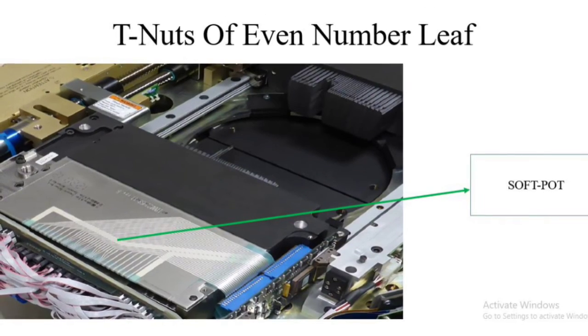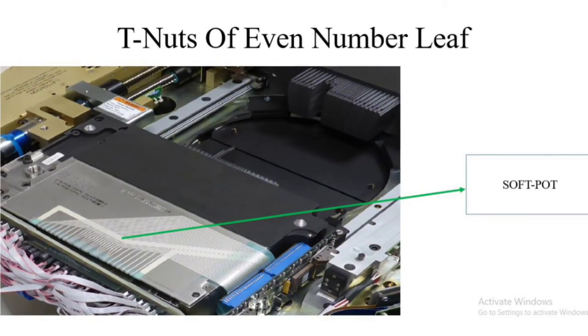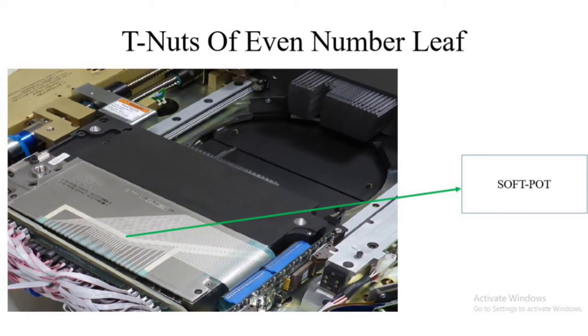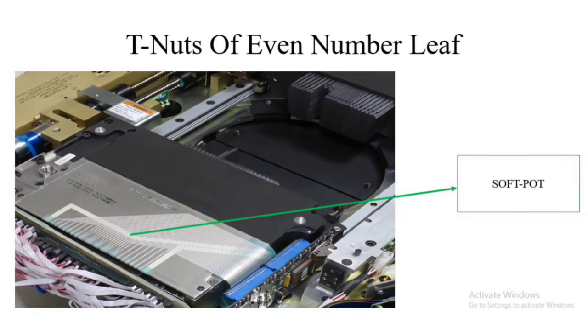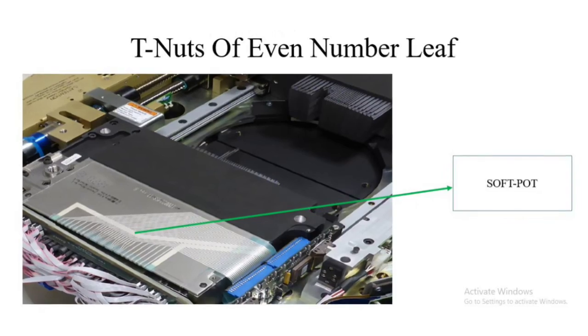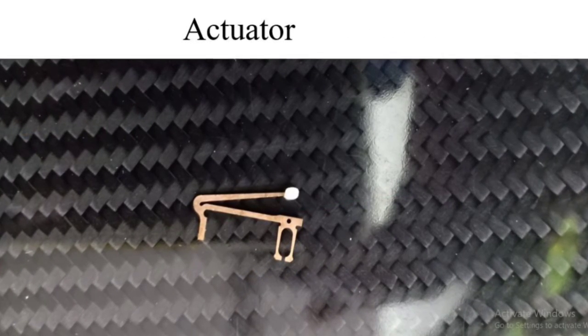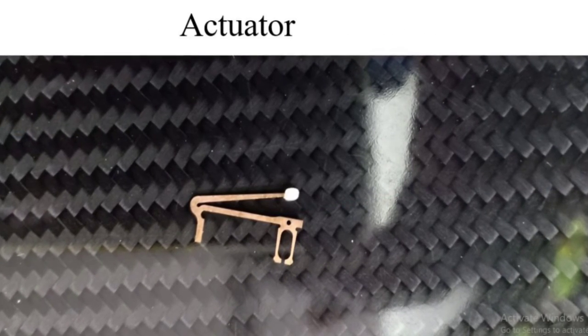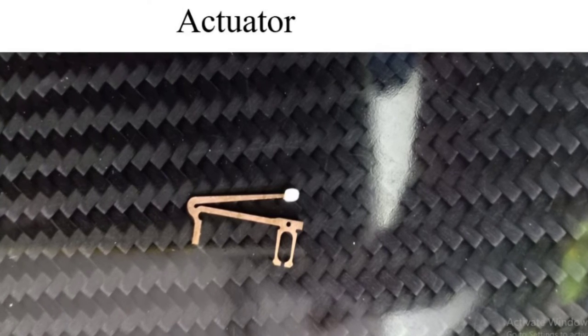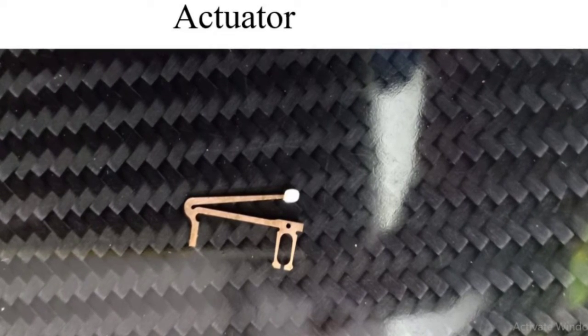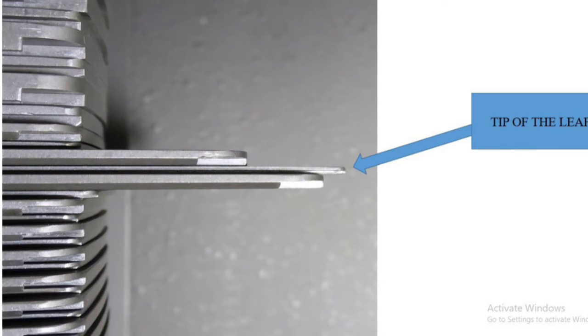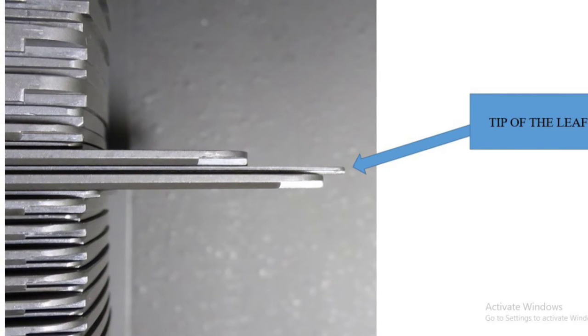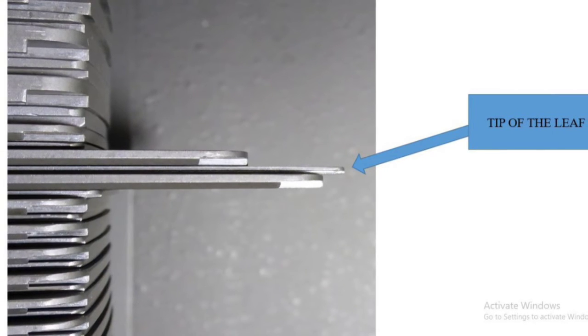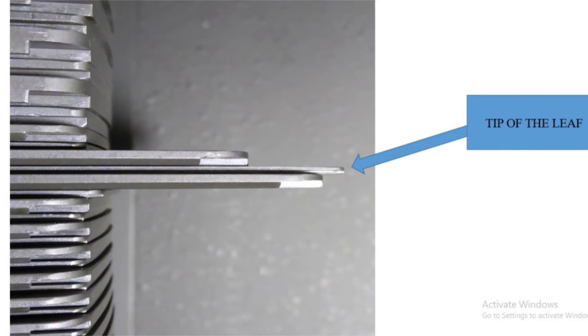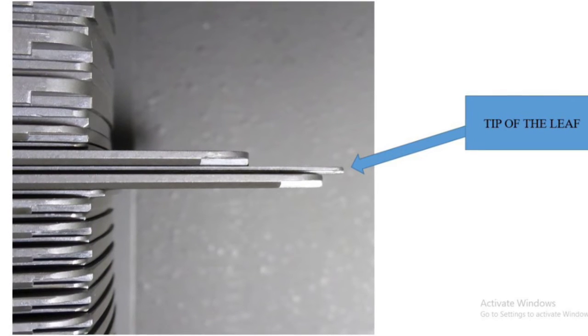This is the soft-pot, and it's nothing but a potentiometer having a track line for each MLC leaf that is attached with the leaf actuator. Now remove the screws on the soft-pot and lift the soft-pot, and you will see all the even number MLCs with actuators. Then remove the actuator of the stuck MLC. Now slowly remove the MLC by holding at the tip. Before removing the MLC, make sure that the opposite carriage is retracted fully. While removing the MLC, you must collect the broken piece of T-nut.